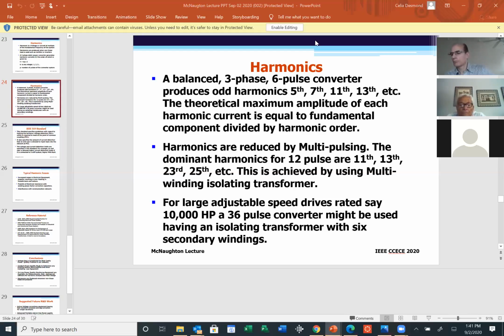Therefore, the transformer design has to be special and take into account all these six-pulse harmonics in the transformer. Next slide, please.